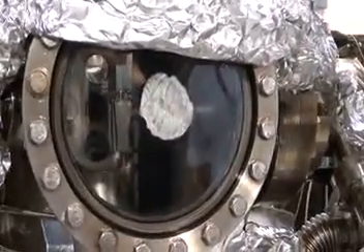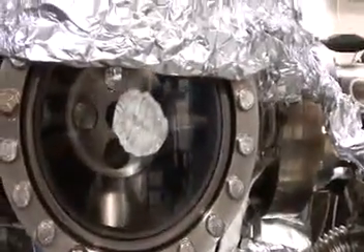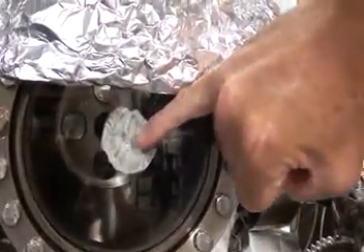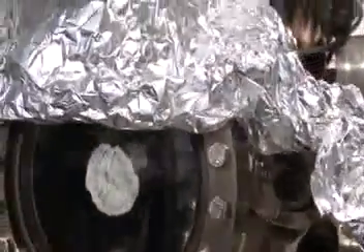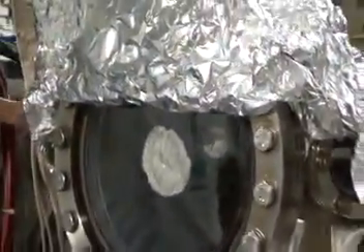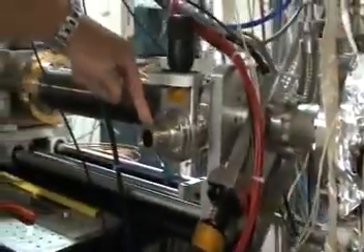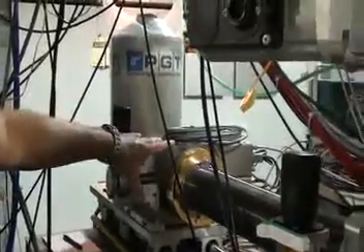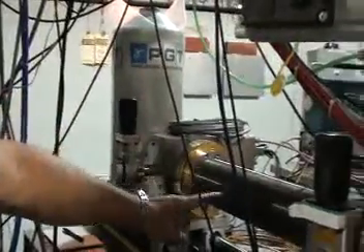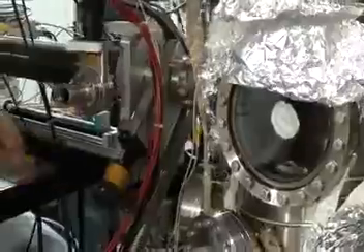This is a sample post on the Brookhaven National Lab. Green dot at the center of the fluorescent white paint is the X-ray beam line. The MEA is behind the chamber with the closed gate valve. Gate valve is here. Pump out port for the bellows is here. There is the bellows. This is the vacuum chamber for our system. The end cap is inside this bellows under vacuum right now. We're fully retracted out of the column with the gate valve closed for preparation for the sample shortly.